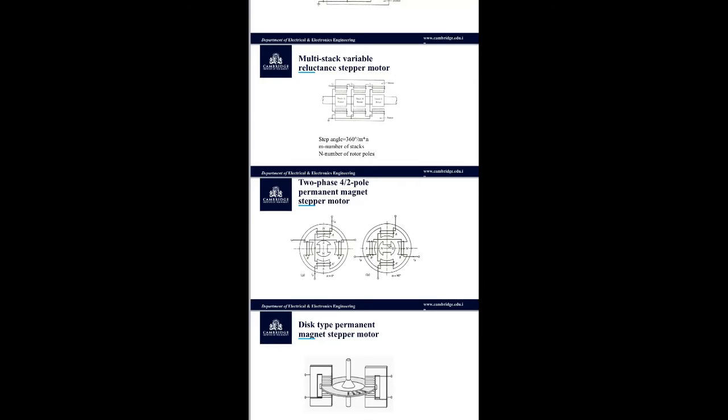From the second one, you all see the figure, that is phase A is excited here. When phase A is excited with the direction of current IA, north pole of the rotor will align with the phase A pole on the left. The rotor turns 90 degree when excitation is switched from phase A to phase B.